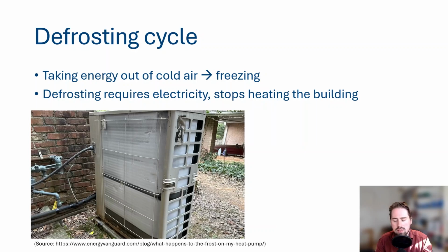So what they need to do is, instead of cooling down the air, heat up the heat exchanger to melt the moisture and let it evaporate. Because during this defrosting cycle, the heat pump typically looks like it's on fire, but it's just evaporating the water. That means that when it's doing that, it stops heating your building.